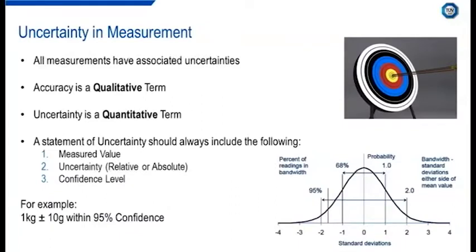It's a common misconception that measurement is an exact science. In fact, all measurements are merely estimates of a true value being measured, and the true value can never be known. An estimate implies that there is some degree of doubt about the accuracy of that measurement. All measurements, therefore, have associated uncertainties. Uncertainty of measurement gives an indication of the quality or reliability of a measurement result. The most important point to note when discussing the uncertainty in measurement is that accuracy and uncertainty are very different terms. Accuracy is a qualitative term with no numerical value.